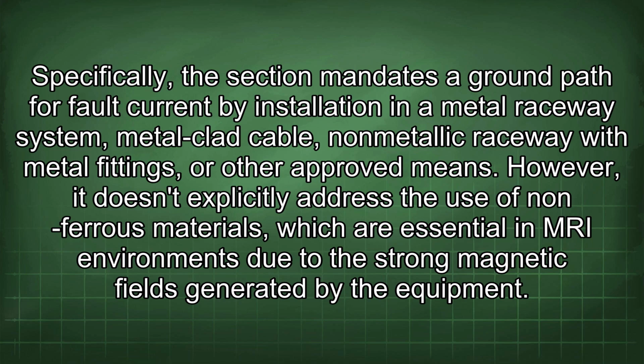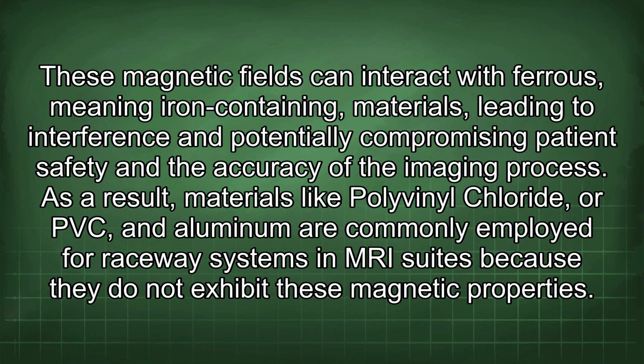However, it doesn't explicitly address the use of non-ferrous materials, which are essential in MRI environments due to the strong magnetic fields generated by the equipment. These magnetic fields can interact with ferrous, meaning iron-containing, materials, leading to interference and potentially compromising patient safety and the accuracy of the imaging process. As a result, materials like polyvinyl chloride, or PVC, and aluminum are commonly employed for raceway systems in MRI suites because they do not exhibit these magnetic properties.